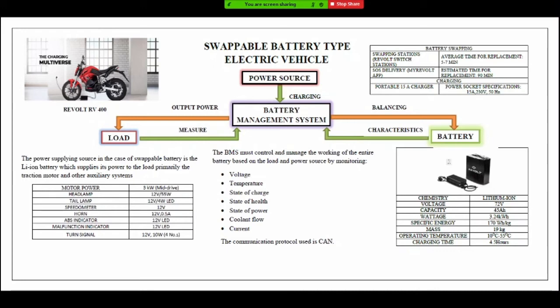You also have safety operations of the battery. The BMS has an internal switch, either a relay or a solid state device, which disconnects the battery from its power source or load if it crosses a boundary of operation. So you control the current or voltage the battery operates on, and control the power source it's getting power from.